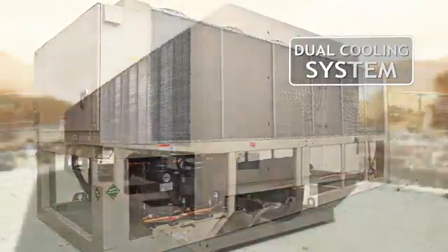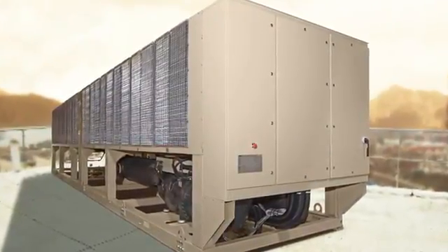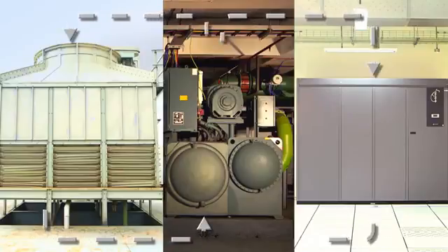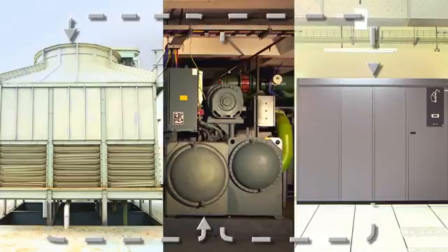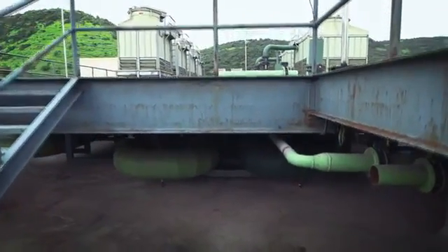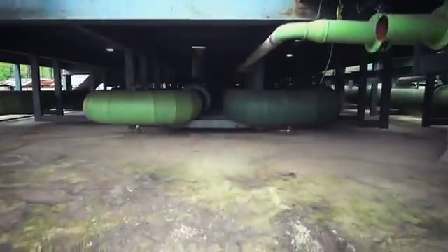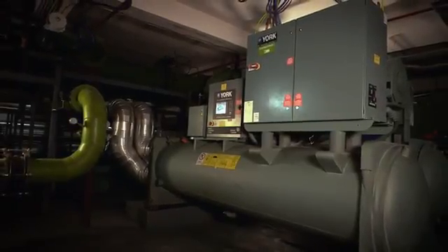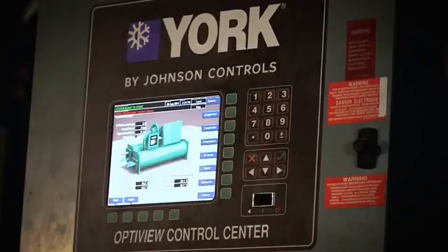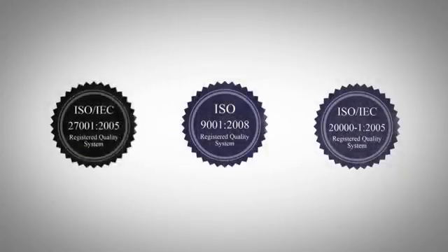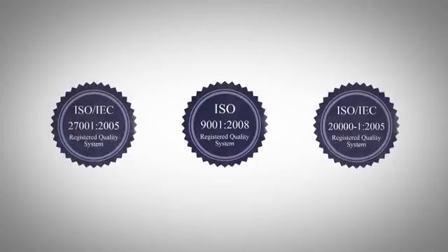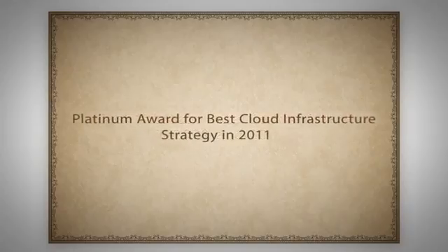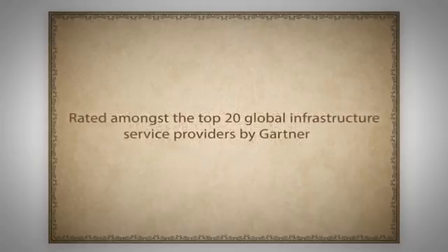The cooling system uses water as well as air-cooled chiller systems to support high-density cooling requirements. The PAHUs configured in N+2 redundancies with automatic dual power supply feeds allow optimized, uniform and clean airflow to the racks. The chilled water distribution with a dual loop piping provides concurrently maintainable mechanical system. The Sify Cloud Center is designed for optimized power usage effectiveness even on partial load. Every feature of the Sify Cloud Center, right from the technology employed to the minutest infrastructural detail, is testified by international standards of quality. And over the years, with the many firsts in the industry, came many more honors and awards.